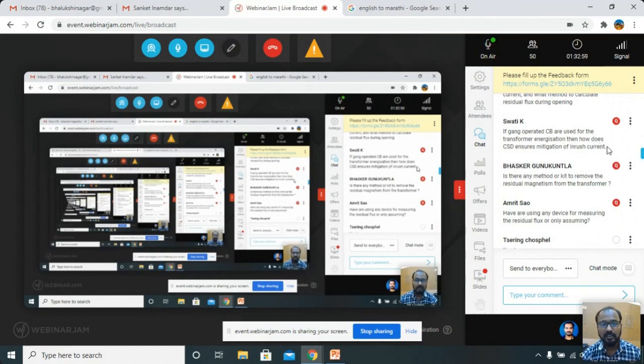inrush current? So for the gang operated CB, we have control. We can control the operation with reference to targeting one pole only. So we can try to minimize the inrush current for the gang operated CB, but we cannot completely minimize it, because we cannot individually operate all three poles, and we cannot control the Y and B poles. But we can target the R pole, open and close the R pole at a precise electrical moment, and minimize the inrush current.